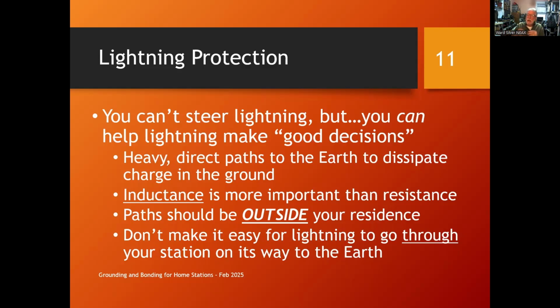The more inductance you have, and depending on the rate of change of current, that causes the voltage across a conductor. Let's take a piece of number 12 that's 1 foot long. And if I hit that with a current surge that is changing at the rate of 1 kiloamp per microsecond, okay? So that's a pretty fast change, but that's typical for a lightning pulse. 1 kiloamp per microsecond across this 1 foot piece of number 12 wire will create a potential difference of 761 volts. That's a straight piece of wire. It's not doing anything. It's not connected to anything. It's just sitting there. And if it has a current pulse like that going through it, you'll get 700 plus volts across it. So minimize the inductance. That's much more important than resistance.